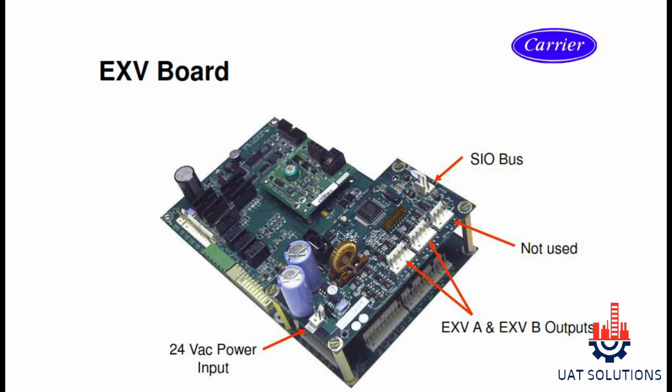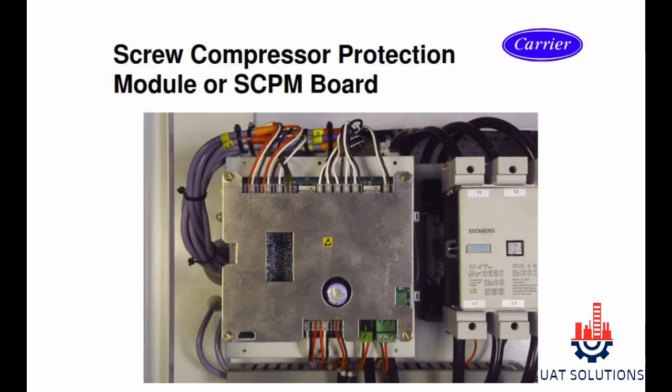All the connections on the board are marked with arrows and show the positions on the EXV board. The SIO bus is used for communication with other boards in the chiller. EXV A and B outputs are used to connect the expansion valves for circuit A and B, and 24 volt AC to power up the board.